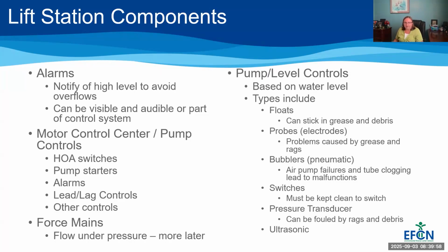So there are some possible issues there. Then the next type is mercury float switches. Mercury float switches are one of the most common types in lift stations. They consist of a float that contains a sealed chamber. It has 2 electrodes and a small amount of mercury. When the float's in one position, like vertical, the mercury is pulled away from the electrodes and the circuit opens. But when that float tilts and the mercury gets between them, then it closes the circuit and says that the pump should come on.